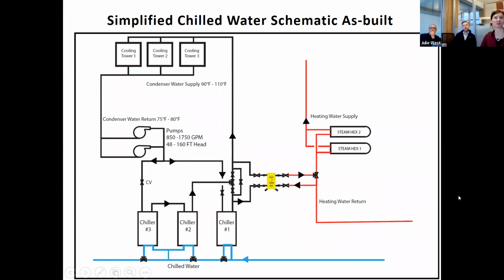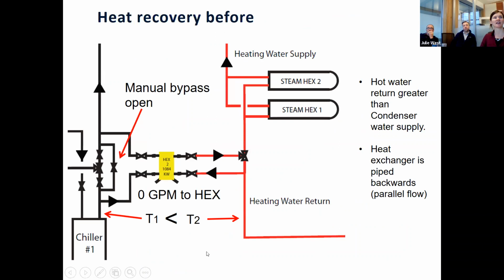So this is a simplified chilled water schematic for the building. These are the three chillers. This is the chilled water line, and this is the condenser water loop that rejects heat out of the cooling towers. There is a heat recovery hex here that was supposed to be recovering heat to the heating water line. But when we looked into it, what we found is that the temperatures were set so that it wouldn't have been possible to actually reject heat into the heating water line of the building, because the temperature that it was set at for the supply water temperature was just too high, so you couldn't bring heat over from the condenser water loop to that side. Hopefully I'm not going through this too fast.